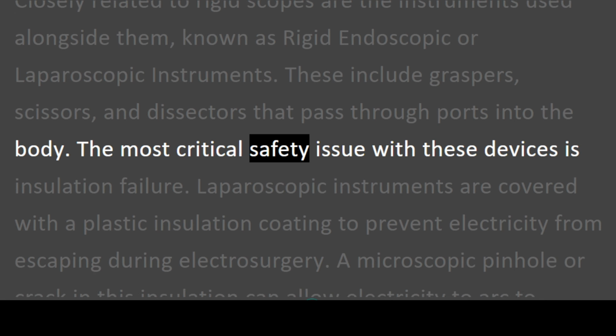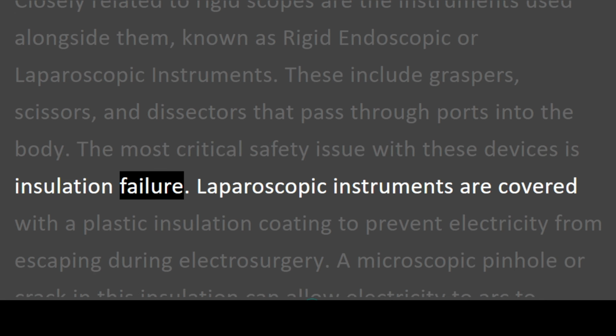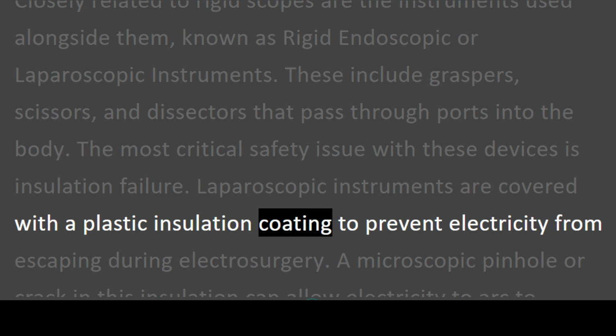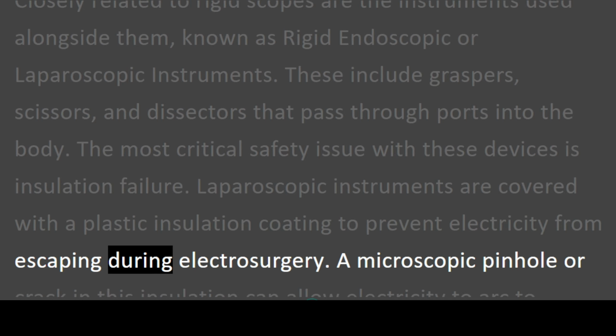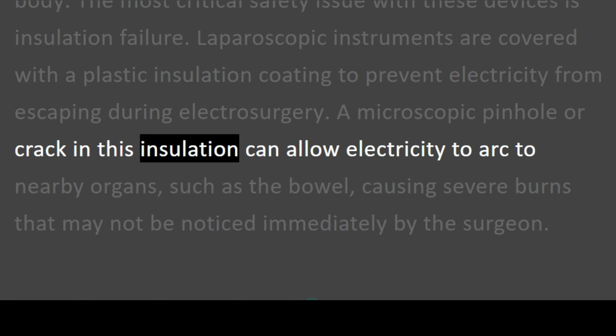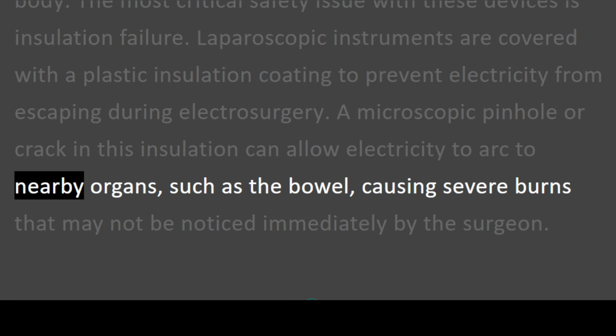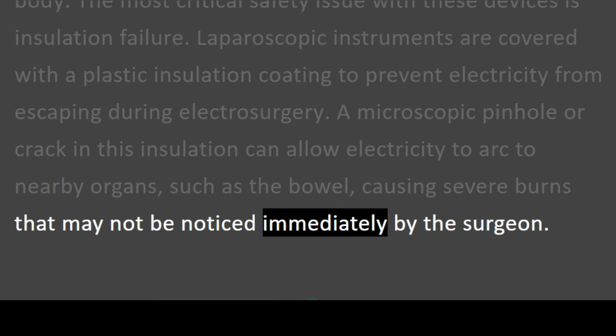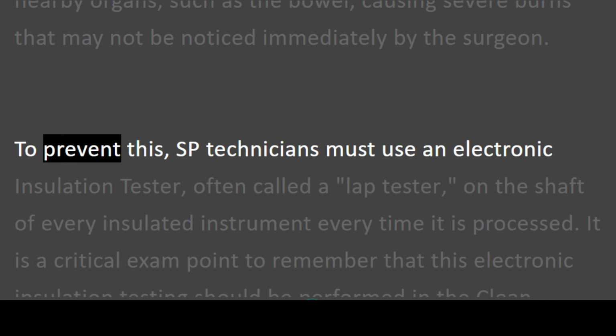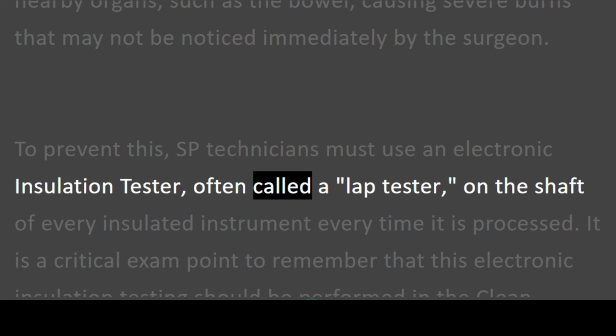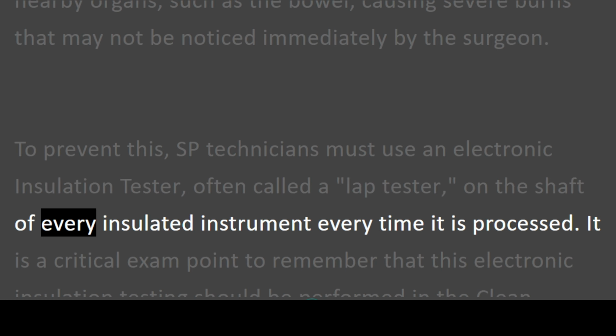The most critical safety issue with these devices is insulation failure. Laparoscopic instruments are covered with a plastic insulation coating to prevent electricity from escaping during electrosurgery. A microscopic pinhole or crack in this insulation can allow electricity to arc to nearby organs, such as the bowel, causing severe burns that may not be noticed immediately by the surgeon. To prevent this, SP technicians must use an electronic insulation tester, often called a lap tester, on the shaft of every insulated instrument every time it is processed.